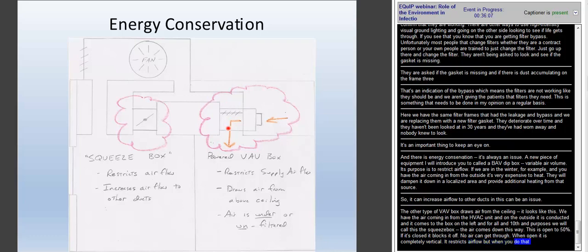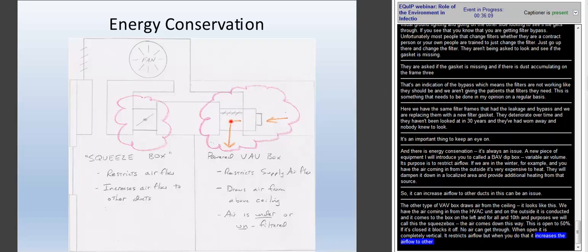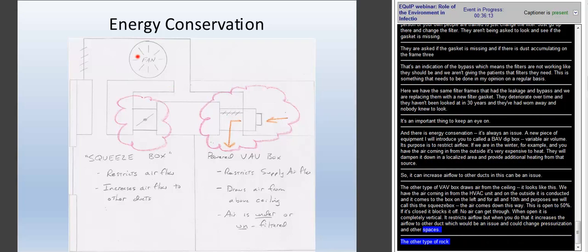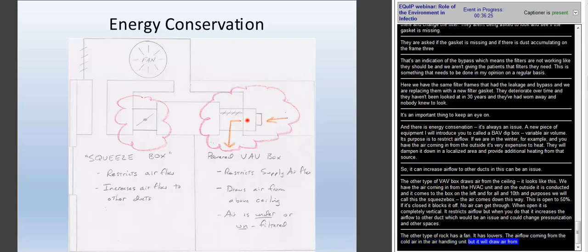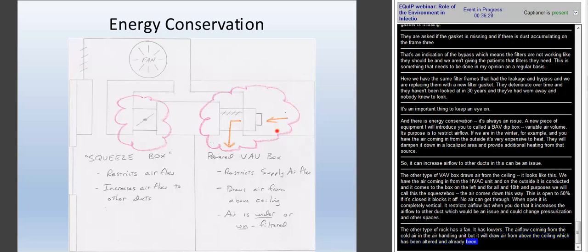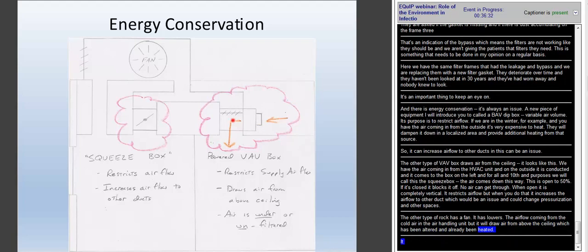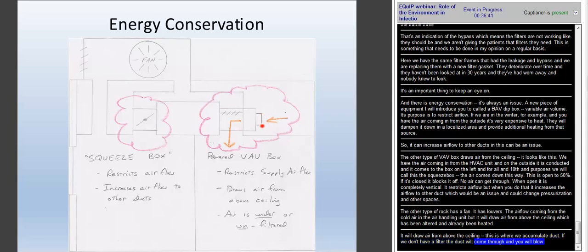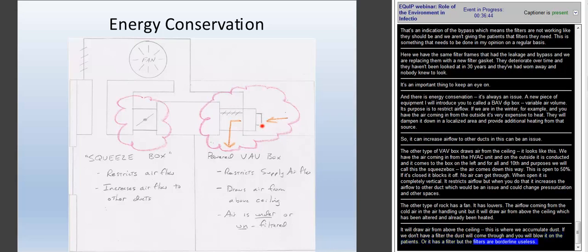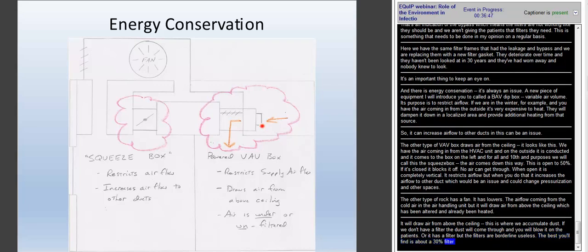The other type of VAV box has a fan in it. It's a powered VAV box. It has louvers that will stop the airflow coming from that cold air from the HVAC unit, from the air handling unit, but it will draw air from above the ceiling, which has already been filtered in theory and already been heated. So it'll draw air from above the ceiling, but above the ceiling is where we accumulate dust. So if we don't have a filter here, that dust is going to come through and you're just going to blow it down on our patients. Or it has a filter, but those filters are really borderline useless. The best you'll find for them is about a 30% filter, a MERV 7, but typically they're just an open fabric filter that doesn't catch very much dust at all. And that can be an issue if we have these where our patients are.